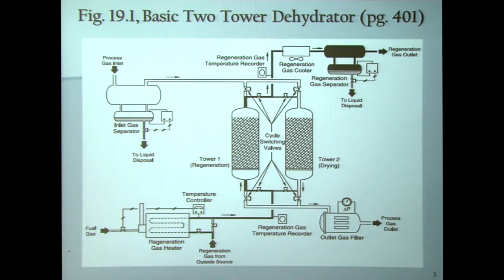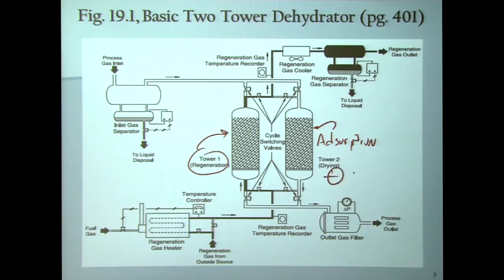While all this is going on, and this vessel is in the adsorption stroke, you have this vessel over here which needs to be regenerated. It's a key point that the time that you have for adsorption must be greater than or equal to the time that you have available to regenerate the tower that's going through its regeneration stroke.